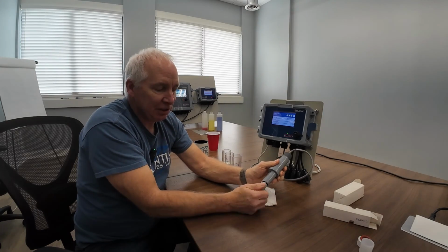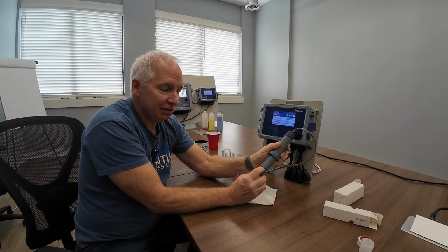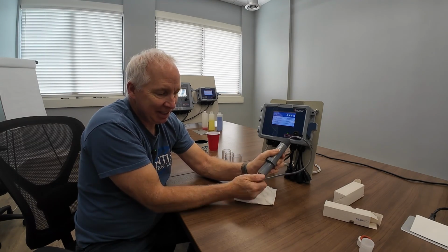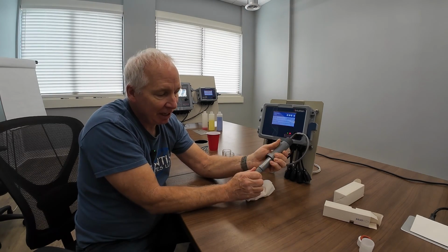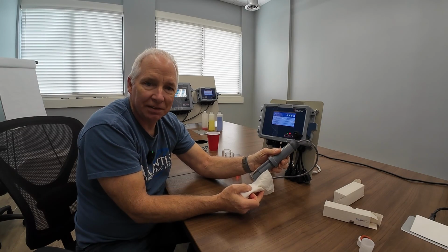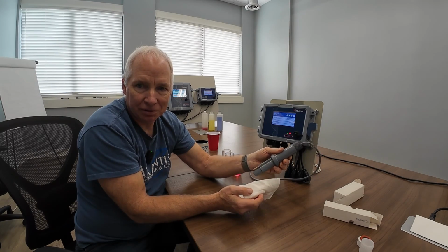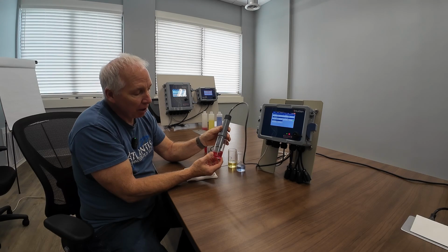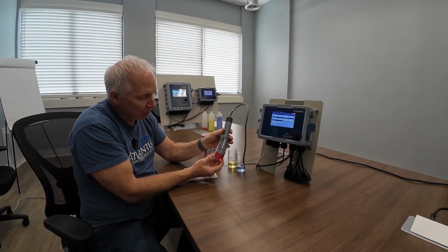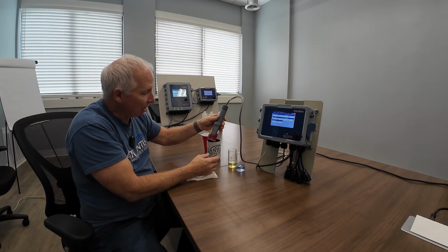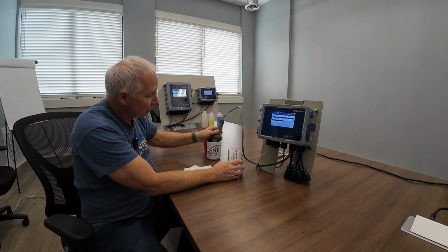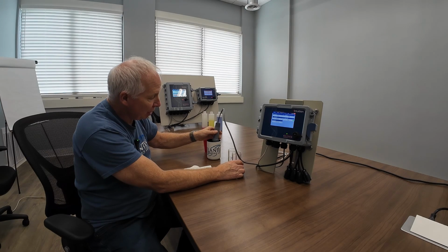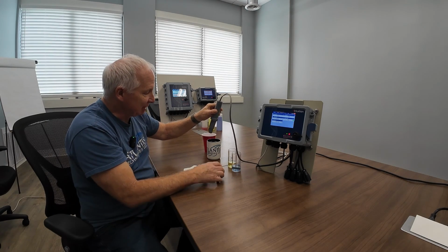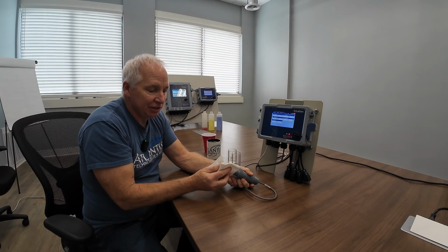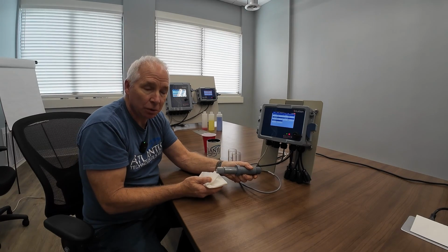So put this in here, push up firmly, start turning, and you want to turn until this O-ring is totally gone. It'll get tight, and now when you look there, you can't see the O-ring. That's sealed. Water won't get in there now. And now you're ready to put this back in the process or in your buffers. You never want to put the flat part of the probe right on the bottom of the beaker or the glass. So I always put it in here on an angle, or I'm resting it on top of here. When I have it sitting inside this cup, you'll notice that I'm trying to put it on an angle so that it's not flat on the bottom of the glass or it's resting up on the probe. When you go to clean a sensor, remember this glass on the bottom is very thin, so you just want to touch it very gently. You don't want to press on it or you'll break it.